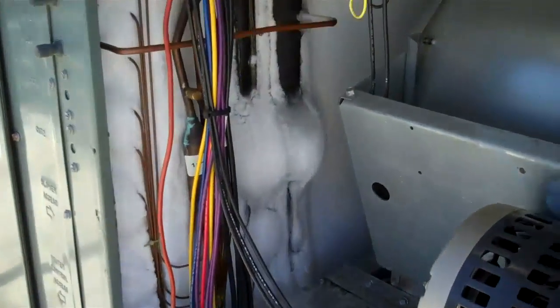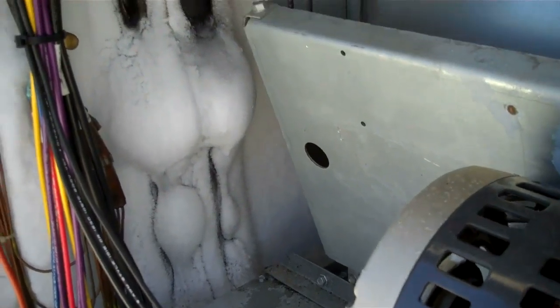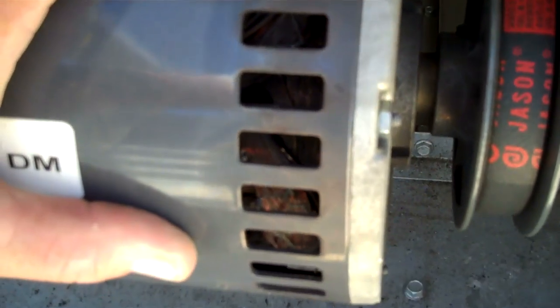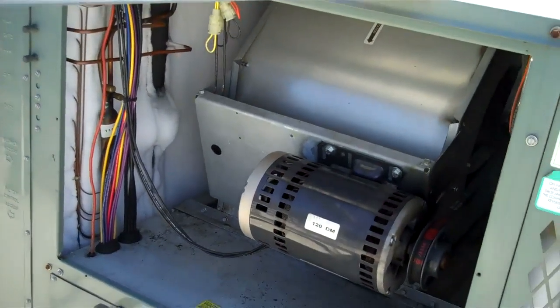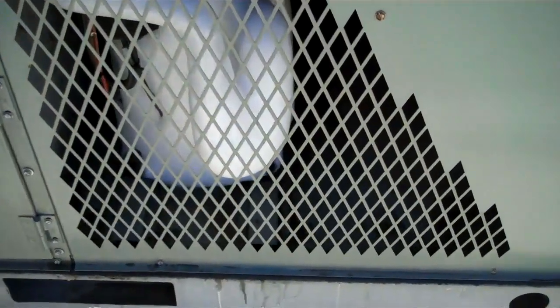I have the blower door off and it is iced up. This indoor blower motor is cool as a cucumber and I see some burnt wiring — that is a bad motor. That thing is iced up pretty bad. I am going to have to order a motor for this so they are going to be down, but this ice is so thick.